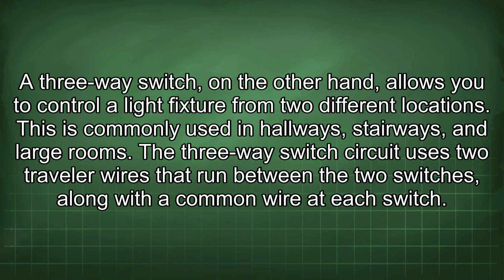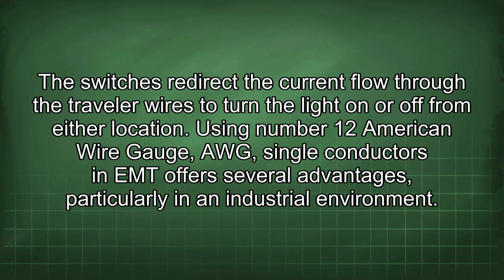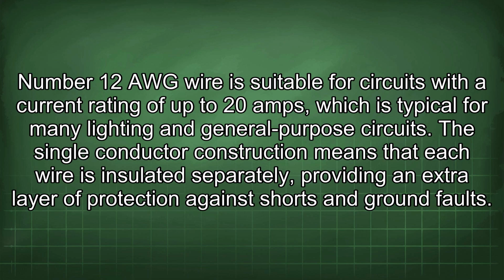The three-way switch circuit uses two traveler wires that run between the two switches, along with a common wire at each switch. The switches redirect the current flow through the traveler wires to turn the light on or off from either location. Using number 12 American Wire Gauge (AWG) single conductors in EMT offers several advantages, particularly in an industrial environment. Number 12 AWG wire is suitable for circuits with a current rating of up to 20 amps, which is typical for many lighting and general-purpose circuits.